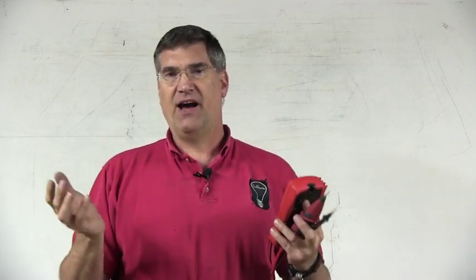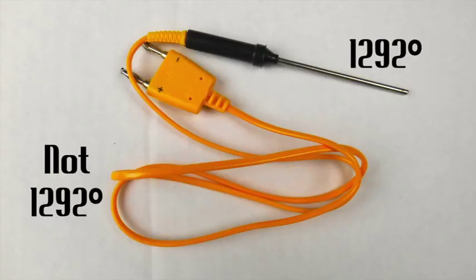As long as you don't put anything other than the probe in 1292, you're going to be fine. The wires, the sheathing, and the insulation, they are not rated to 1292 degrees. They're very high temperature safe, but not to those temperatures. So just be careful that you don't inadvertently put the wiring to the probe or the insulation on the wiring into a situation where it's going to be exposed to really, really high temperatures, because it will more than likely fail. The temperature probe is pretty basic.